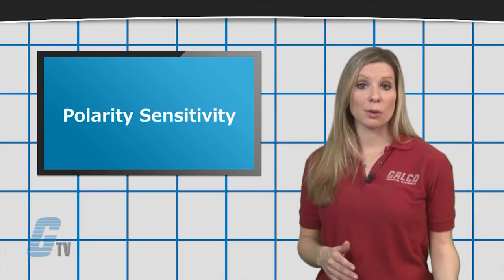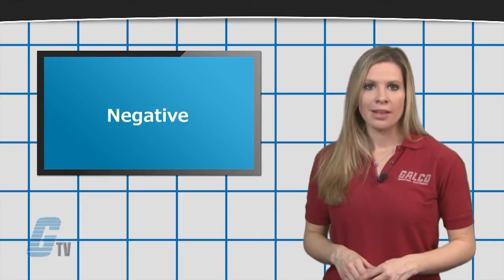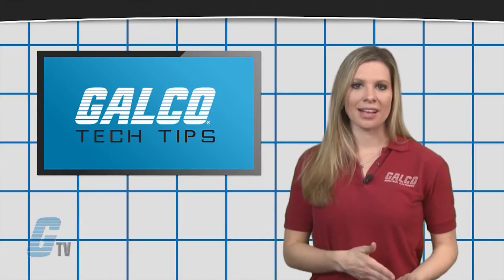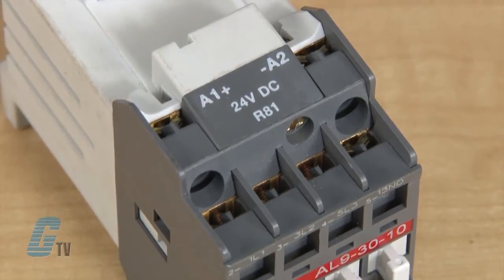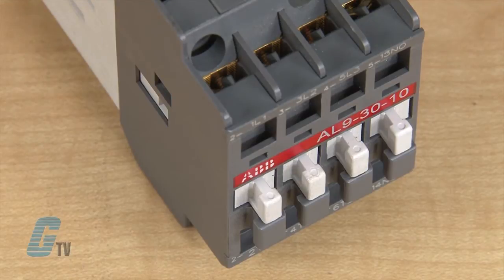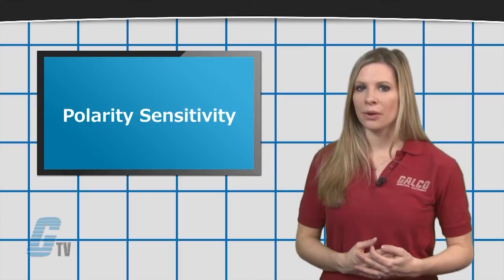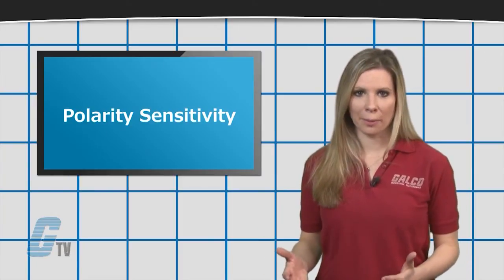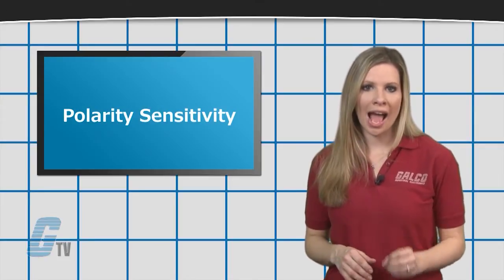In some cases, there may be a positive or negative indication for polarity that may appear on some contactors next to the coil power terminals. Older A-Line contactors from ABB, such as the AL contactors, are one of these contactors that require proper DC polarity when wiring up the coil. If the polarity is reversed, the contactor will not operate.